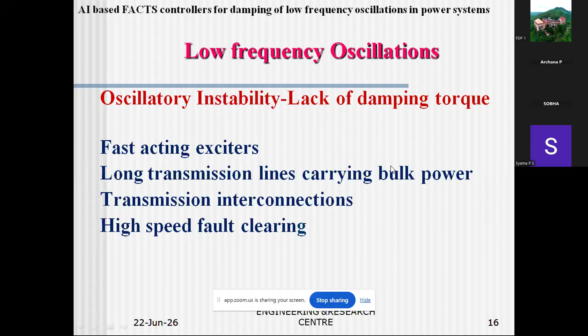Long transmission lines carrying bulk power, always interconnection, are always a threat to stability. All stability issues are more pronounced for long transmission lines and transmission interconnections, especially weak interconnections. Then high speed fault clearing. High speed fault clearing means, for a transient, a sudden disturbance, you have to clear that very fast. But if you are doing that, it will affect the damping of the system. So all these are situations under which there is a lack of damping torque, and it may result in oscillatory instability, that means growing low frequency oscillations.